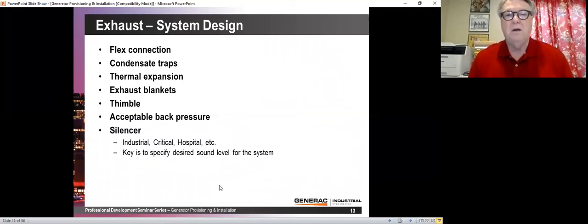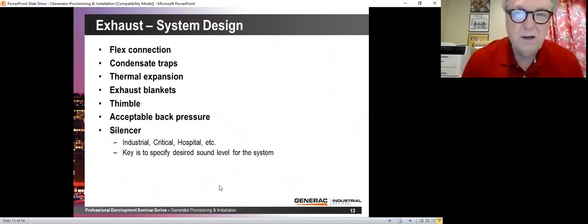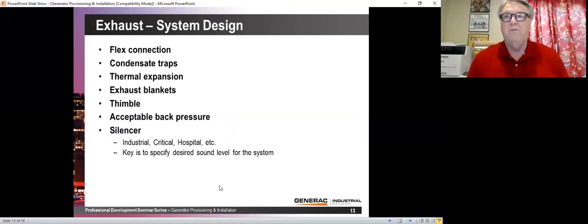There is typically not a great deal of difference sound-wise between critical and hospital grade. Generac, on all of their industrial generators, will provide a critical silencer standard, and they tend to be very quiet. But you should never look at the silencer and determine how loud the generator is going to be from the silencer, because there are lots of other sources of sound within the generator. So we see specs sometimes that want to know what the dBA is of the silencer, and 10 feet from the silencer, it doesn't say which direction from the silencer. Not a good way to specify these things.